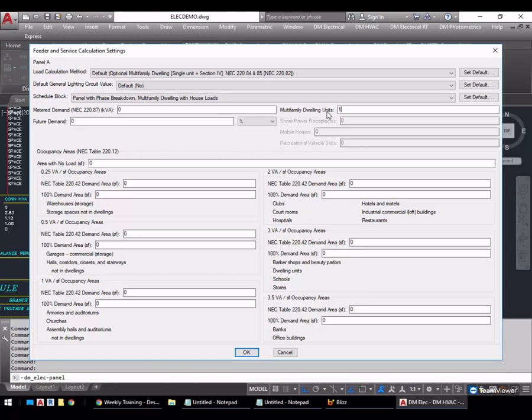But then in the panels upstream, don't set the values additionally because you'll end up double counting. It'll be pretty obvious when you look at your totals that they're twice what they should be, and so you'll know to go back and change them. But it's simplest if you just set it up right ahead of time. I'm eventually going to create a couple panels underneath this one, so we'll leave that at 0 for the moment.